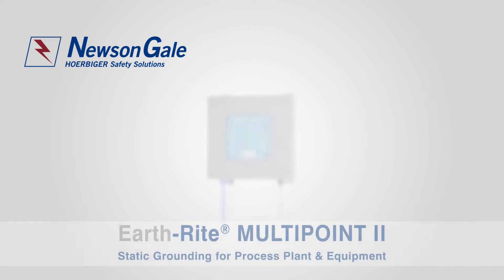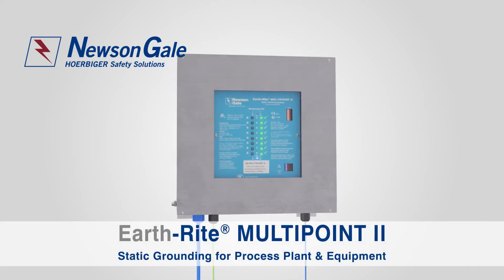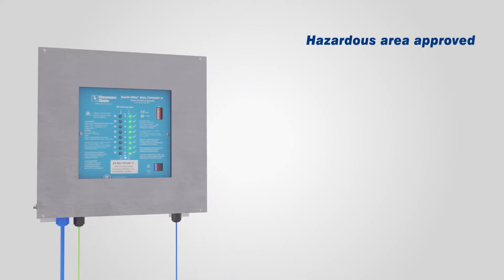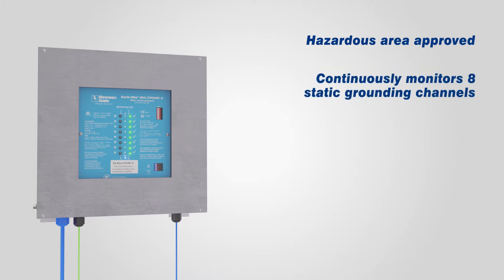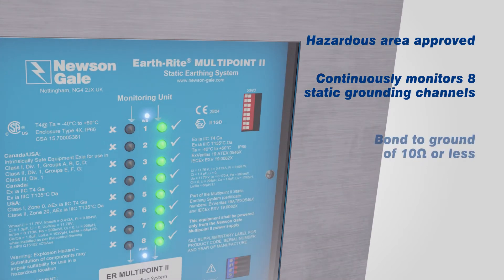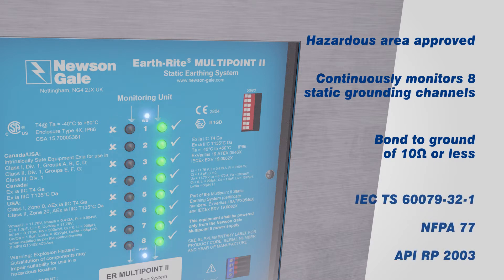The EarthRite MultiPoint 2 is Newson Gale's latest solution to multi-channel static ground monitoring for the hazardous area industries. Each unit is fully certified and capable of continuously monitoring up to eight independent static grounding channels, ensuring each connection achieves a low resistance bond to ground of 10 ohms or less, demonstrating compliance with the best practice approach stated in IEC TS 60079-32-1, NFPA 77 and API RP 2003 guidelines.